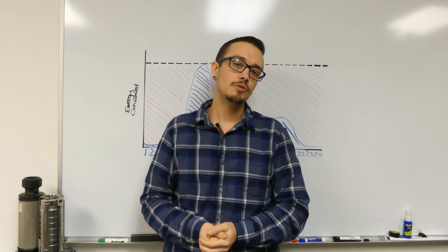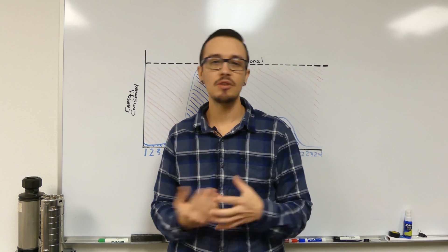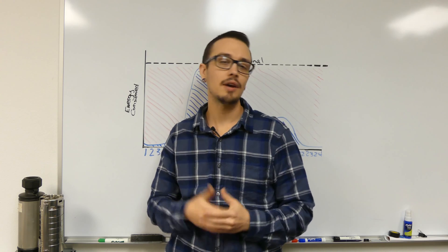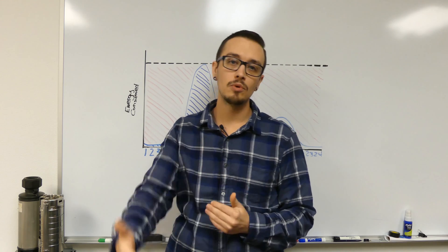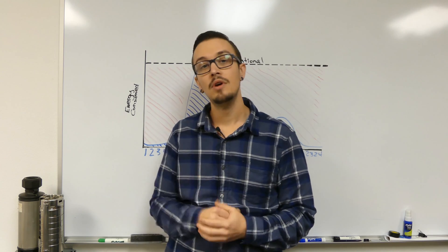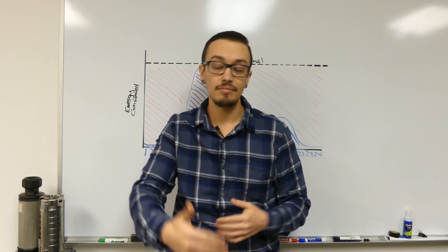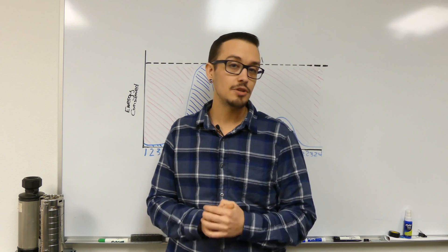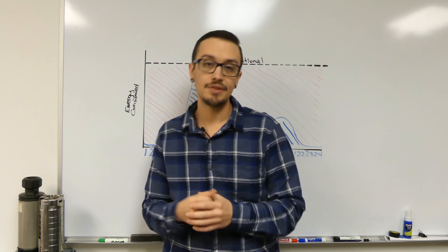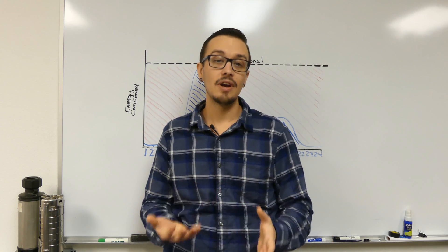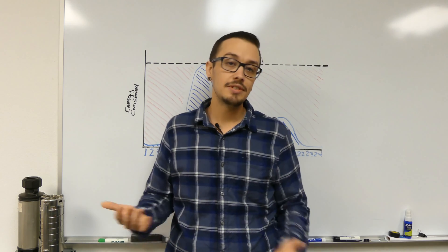Another situation that I like to use VFDs is when we've got exceptionally deep wells or exceptionally long wire runs. The benefit of three phase motors is your wire sizing requirements change as compared to single phase motors. You've got one more leg that you're able to send power through. So your wire sizing is generally reduced by quite a lot. So when you've got a five, six, seven, eight hundred foot well, you could potentially look at the cost difference between the wire and the motor and the drive compared to that of a conventional system. And you might find that actually the drive is less expensive because wire is very expensive.